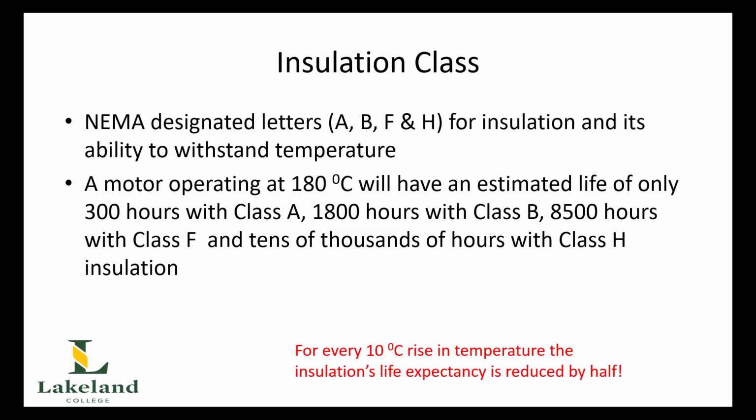The next thing to mention is our insulation class, and once again this is a NEMA rating, and this is either going to be A, B, F or H, and it's going to rate the insulation of the windings with respect to temperature. The reason why this is an important consideration for motor construction is that the higher the insulation rating, the more hours it will be able to withstand running at higher temperatures. Now a surprising rule here is that for every 10 degrees C rise in temperature, the insulation's life expectancy is reduced by half. So that's an amazing consideration.